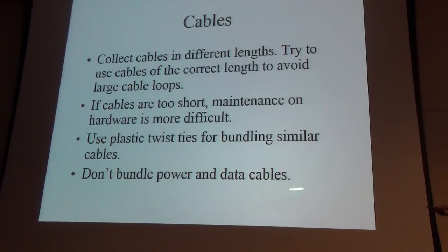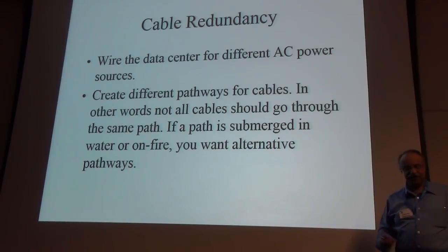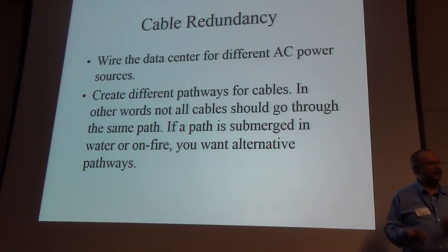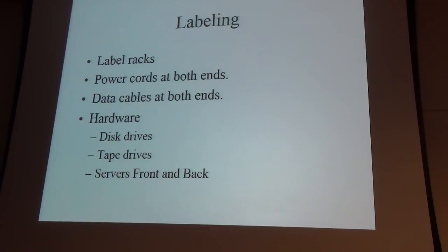One important thing about cables: don't put power and data cables together — keep them separated. That's a very important point. Also have redundant cables, because many cables are actually faulty. You'll hook up everything rows and rows, the link light is on and blinking, but it won't communicate. Turns out the cable is faulty and only passing the signal part of the time. At one place we had a guy whose full-time job was to make sure everything was labeled and kept track of. That's all he did.